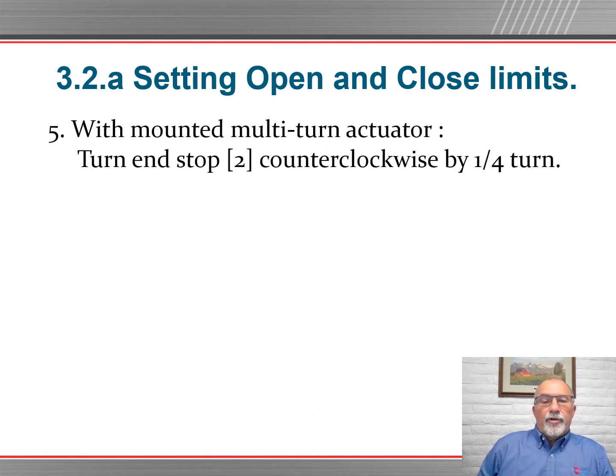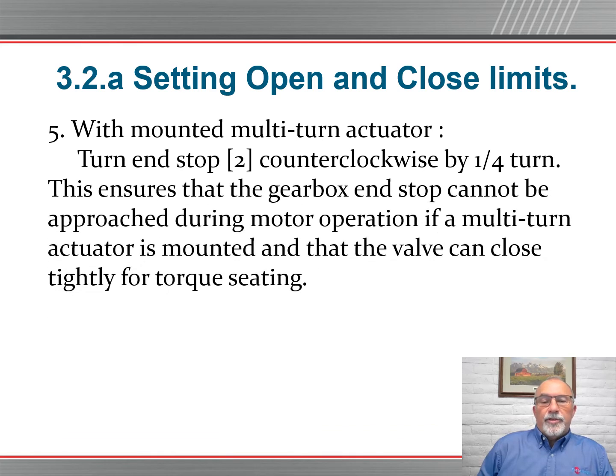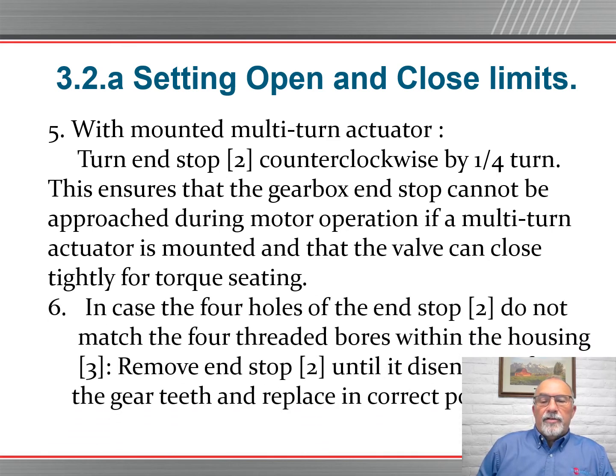With a mounted multi-turn actuator, turn the end stop counterclockwise by 1/4 turn. This ensures the gearbox end stop cannot be approached during motor operation if a multi-turn actuator is mounted, and the valve can close tightly for a torque seating. In the case that the four holes at the end stop do not match the 4 threaded bores within the housing, remove the end stop until it disengages from the gear teeth and replace it in its correct position.